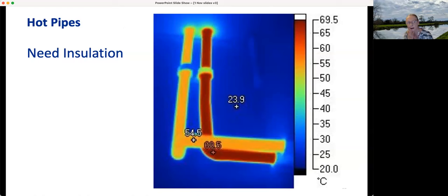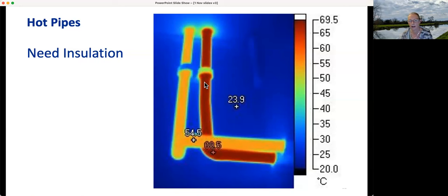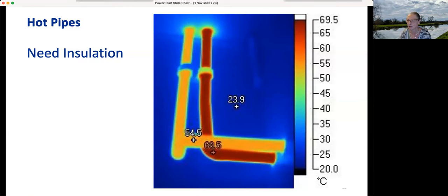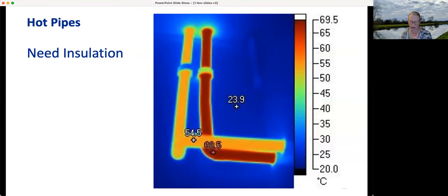This is real heat loss. We're looking at pipes — the yellowy pipe is hot and one is even hotter — leaking heat into the room, or possibly outside. If it's outside, that's definitely a waste of heat. If it's inside, you're not able to control where that heat is going. What's the point in having thermostatic radiator valves if the pipes are heating the place up anyway? If they're hot water pipes for your taps, you certainly don't want that heat even in summertime.